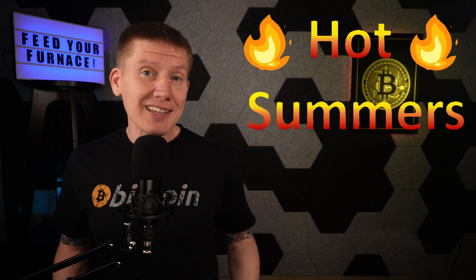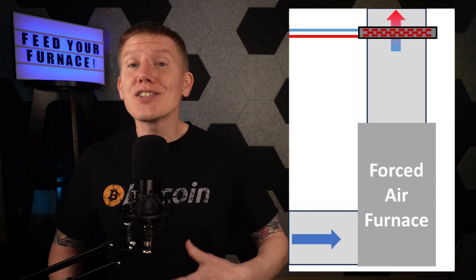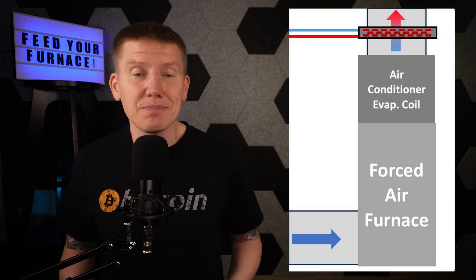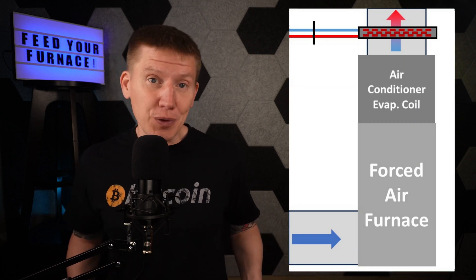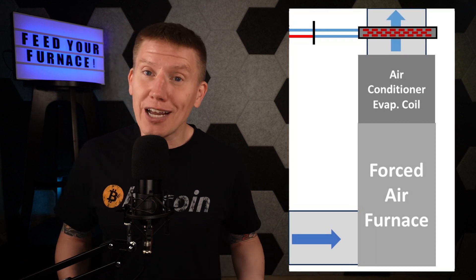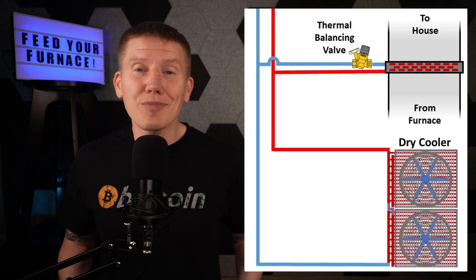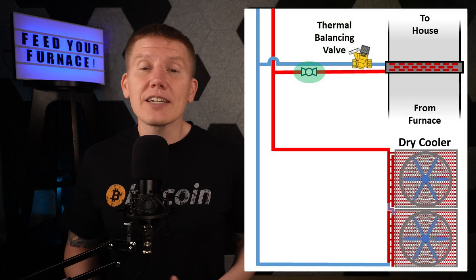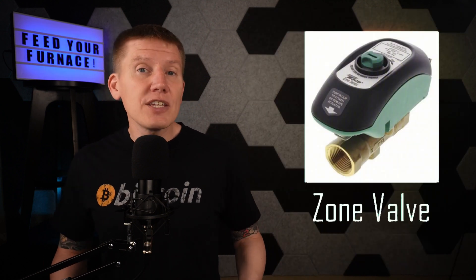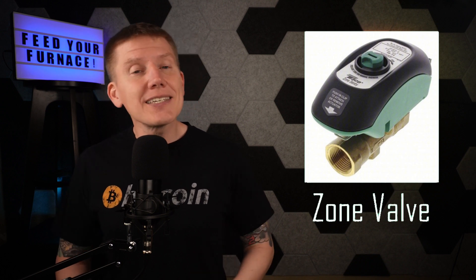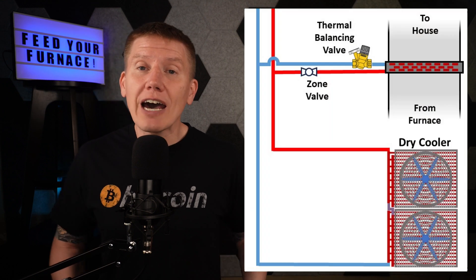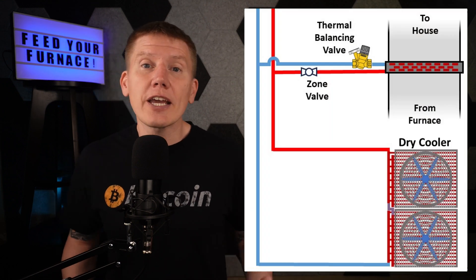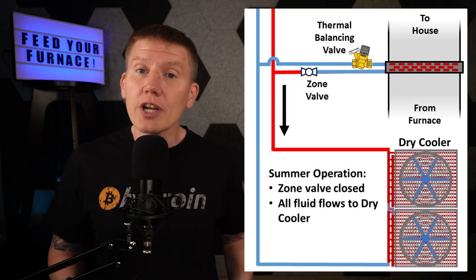Another part of this system to think through is what to do during the summer months. Most likely, the ducting of your forced air heating system is also the ducting of your air conditioning system. It's going to be really important to shut off any fluid from flowing through the radiator, or you might be heating your house when you don't want to. Thermostatic valves are not made to completely cut off fluid flow, so you'll need another valve in line to completely isolate the radiator. This is what zone valves are made for — simple electrically operated valves designed to stop fluid flow to different parts of a hydronic or hot water system. Inserting a zone valve in front of the radiator should isolate it so all fluid is directed to the dry cooler during summer months.